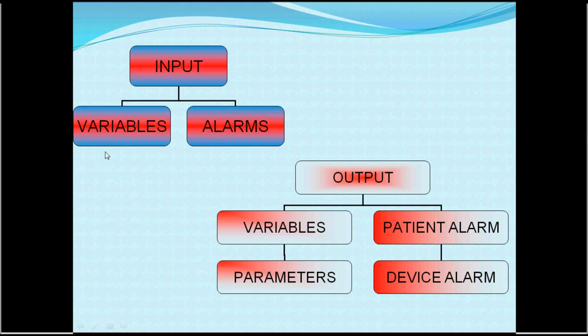The input data consists of the control variables and phase variables that are set for the patient, along with the alarm settings. These are the data which determine and define the character of the breath for the patient.